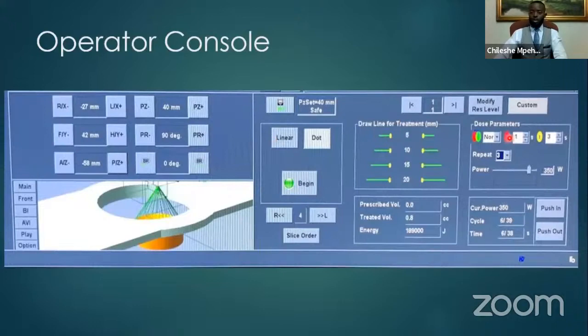On the right, we've got our dose parameter control system. And this basically allows us to tell the machine how much energy to give, number one, as in how much power it should be emitting. And you can see that this picture was taken while I was performing a treatment emitting 350 watts. So I was just coming off a test dose, going up towards the maximum treatment dose of 400 watts, which is what we aim for.